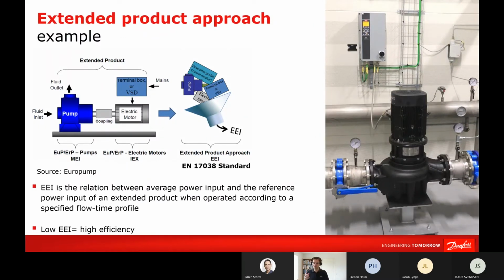What you can see, then, is a drive, a speed drive mounted on a wall, with electrical losses, driving a pump. So you have a fluid, let's say water being pumped here, and you have electrical energy to pump this water. So we have this extended product from the variable speed drive to the water, the fluid being pumped there. The extended product consists of everything you see in this picture: the pump, the electric motor, the terminal box, maybe even the coupling between them, and the losses in the drive.